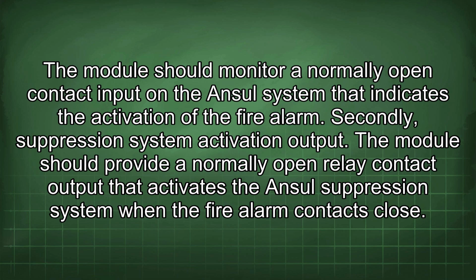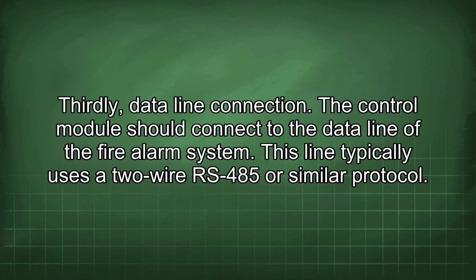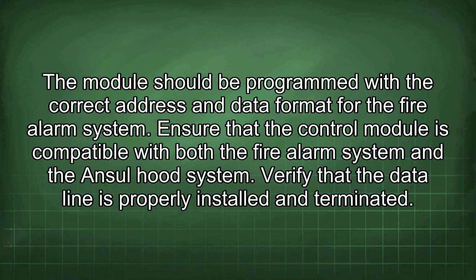The module should provide a normally open relay contact output that activates the Ansul suppression system when the fire alarm contacts close. Thirdly, data line connection. The control module should connect to the data line of the fire alarm system. This line typically uses a 2-wire RS-485 or a similar protocol. The module should be programmed with the correct address and data format for the fire alarm system.